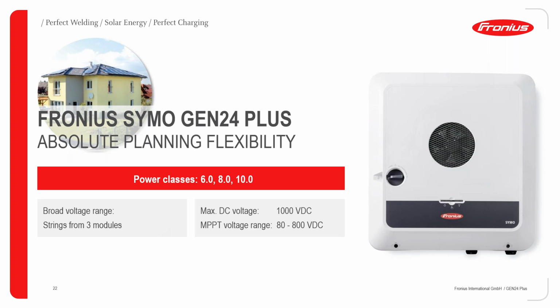The maximum DC voltage is kind of the same as with the previous Snap inverters, 1000 volts DC maximum, and the MPP tracker voltage range where we can operate within is 80 to 800 volts DC. So therefore, from 3 modules on, we can ensure that the inverter is running. As I mentioned, we have 2 individual working MPP trackers, so also east-west installations are no problem, but please be sure to consider the 2 different input currents, 25 amps on the first one, 12.5 on the second one, and 1 battery input capable of 22 amps.